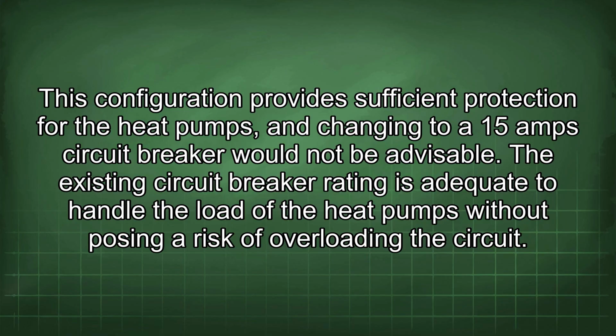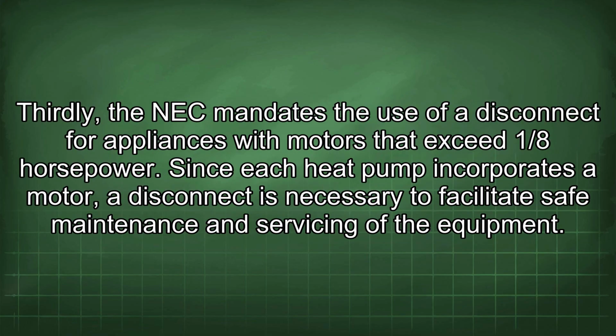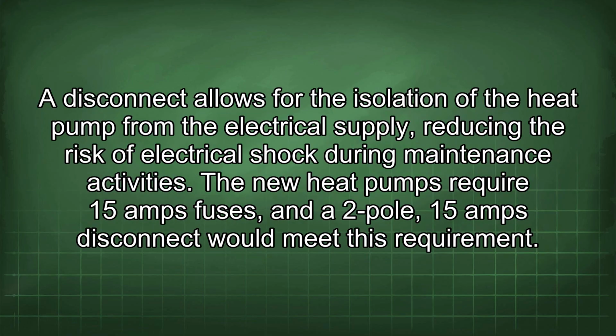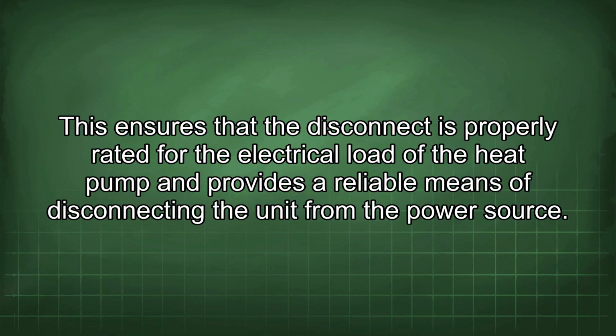of overloading the circuit. Thirdly, the NEC mandates the use of a disconnect for appliances with motors that exceed 1/8 horsepower. Since each heat pump incorporates a motor, a disconnect is necessary to facilitate safe maintenance and servicing of the equipment. A disconnect allows for the isolation of the heat pump from the electrical supply, reducing the risk of electrical shock during maintenance activities. The new heat pumps require 15 amps fuses, and a 2-pole 15 amps disconnect would meet this requirement. This ensures that the disconnect is properly rated for the electrical load of the heat pump and provides a reliable means of disconnecting the unit from the power source.